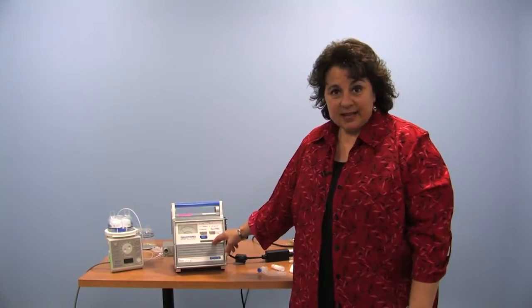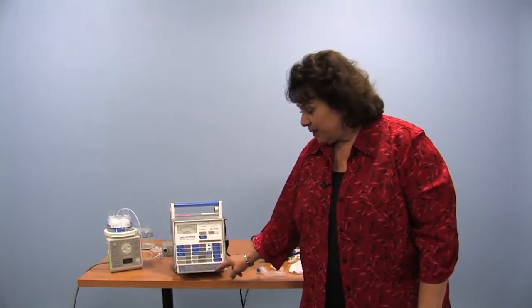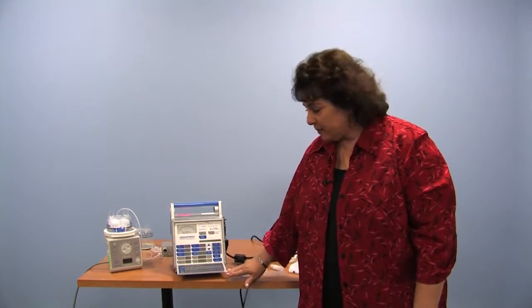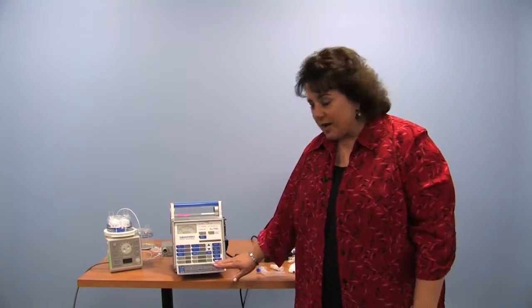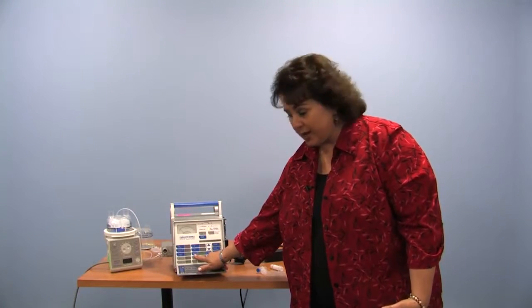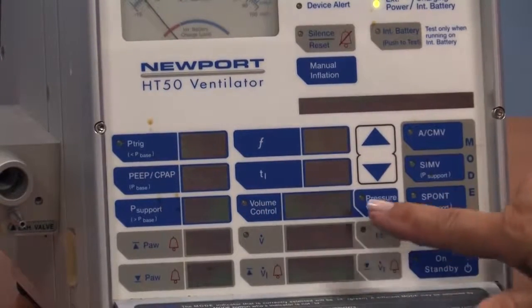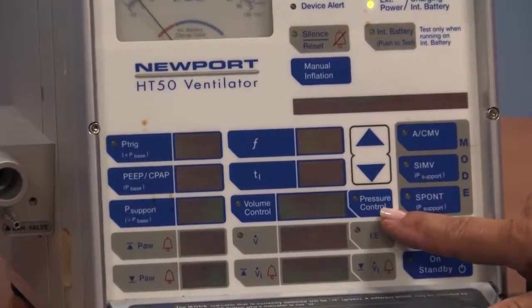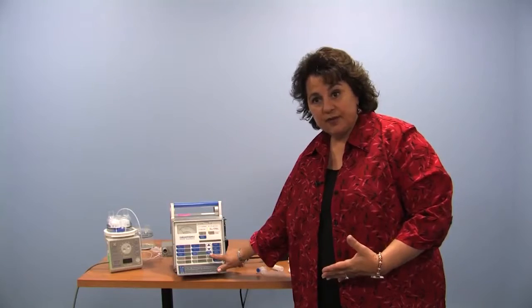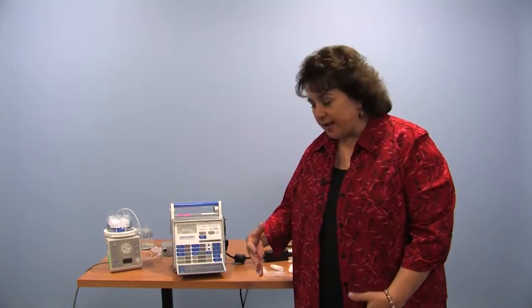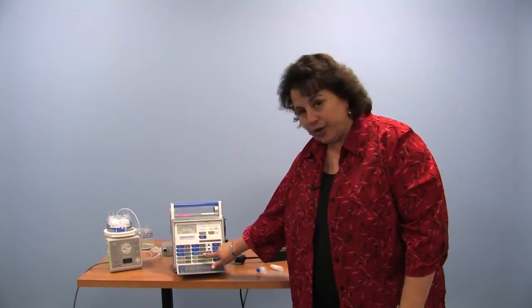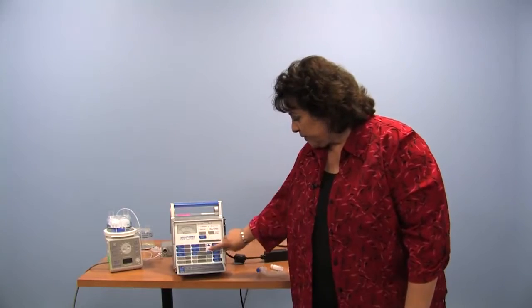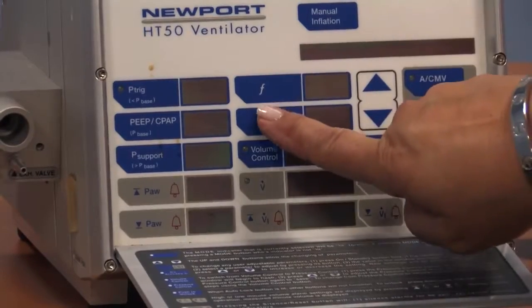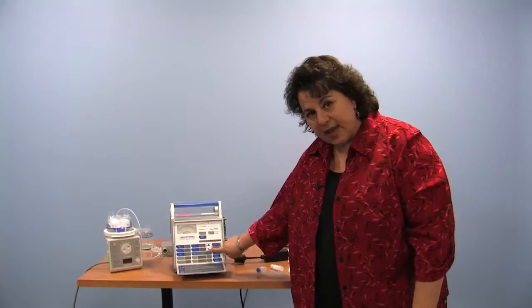Your child's settings on the ventilator can be viewed here under the cover of the front panel. The doctor will prescribe either a tidal volume for a volume breath for your child as set here, or a pressure preset breath, meaning that there'll be a pressure which the ventilator achieves and your child will receive a certain size of breath based on the pressure that's set. You will see the number in this window. All of the parameters can be changed by using the arrows. You select the item and change it by the arrow.